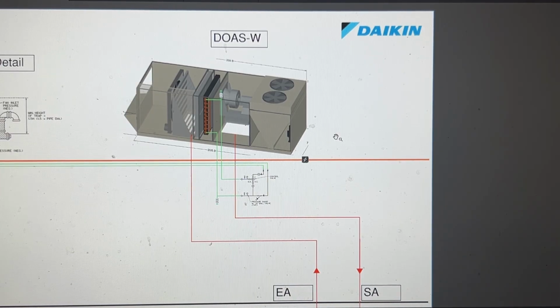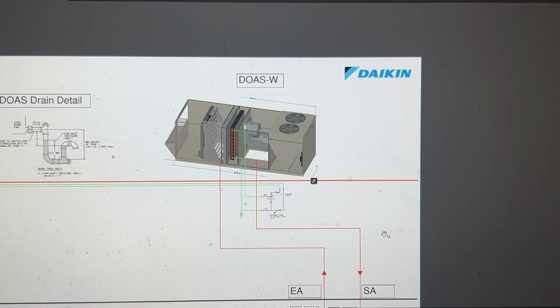So how this building and system is set up is we have our rooftop package unit, and then in the sub basement we have a heat exchanger with a glycol loop and pumps. So I will show you that. I'm going to stick with, we're up here at the unit. This is what the rooftop unit looks like. So that outside air is coming in, and then, depending on what's taking place, what season we're in, it's either the DX coil or the hot water coil, and then that pushes the supply air down to the floors.